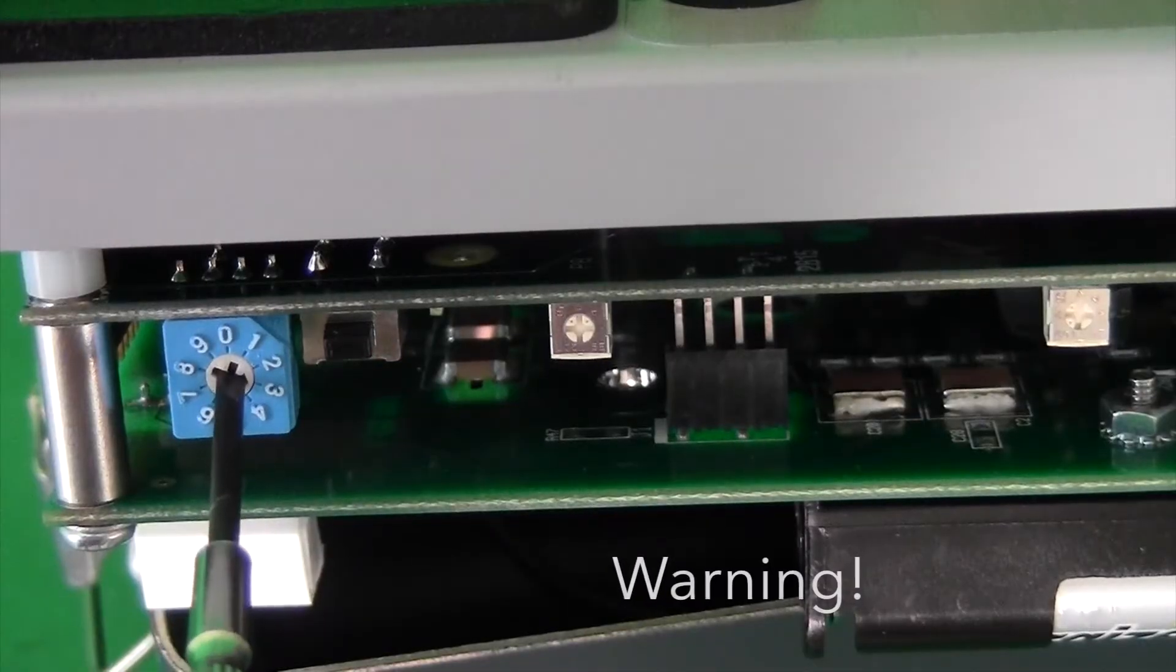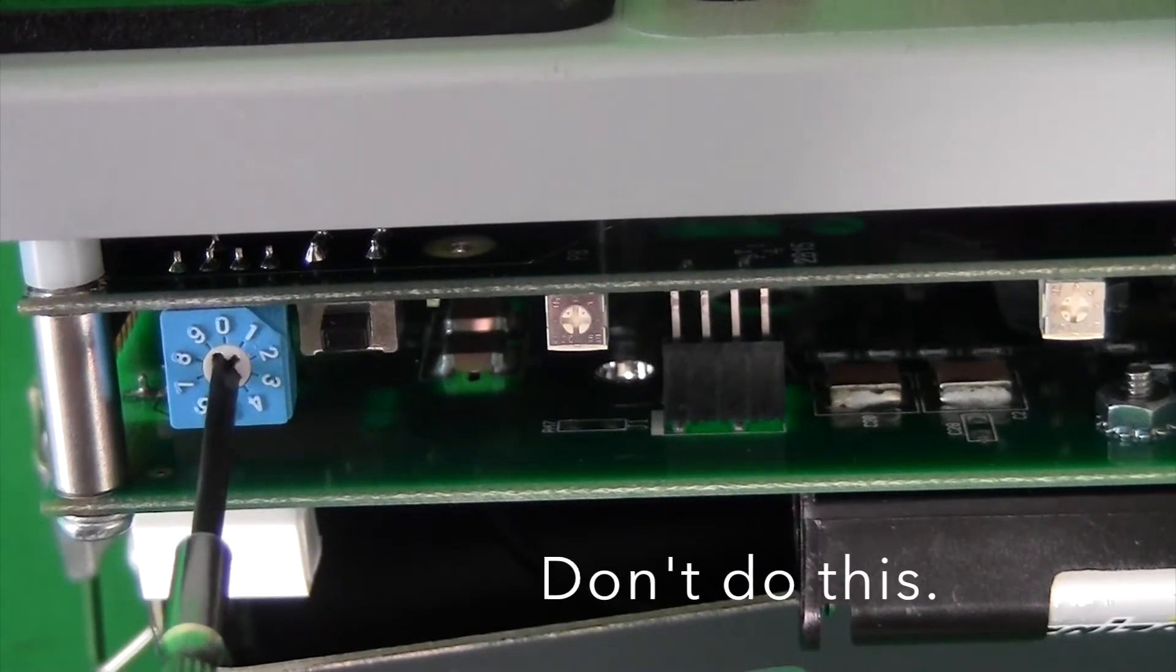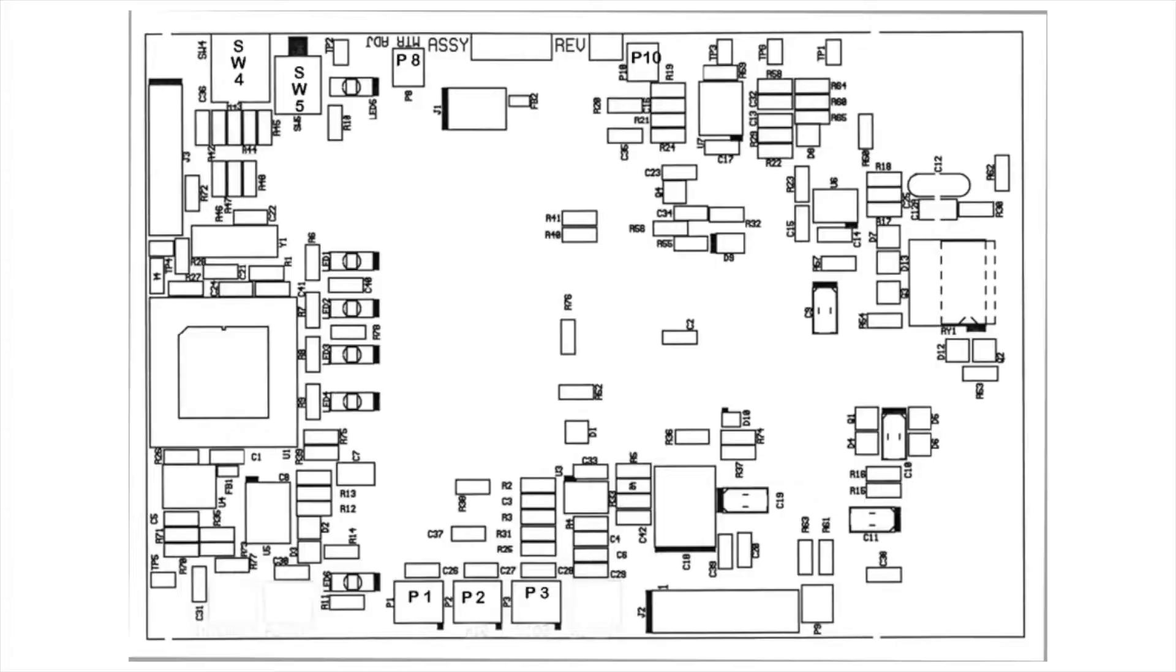Note, be careful not to switch SW4 to other positions, which could adversely affect the calibration. Schematics are available if there is any confusion in finding the internal controls.